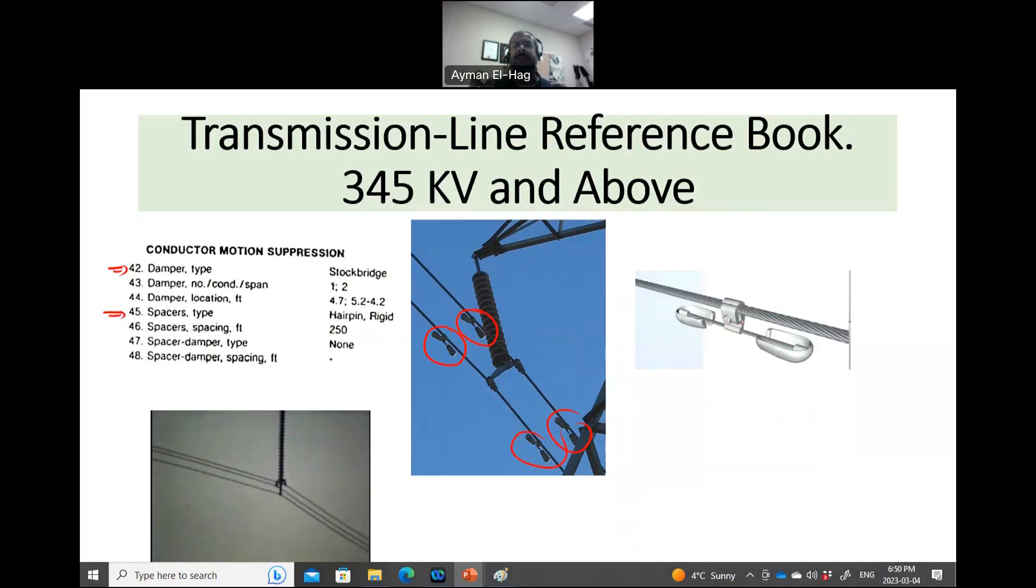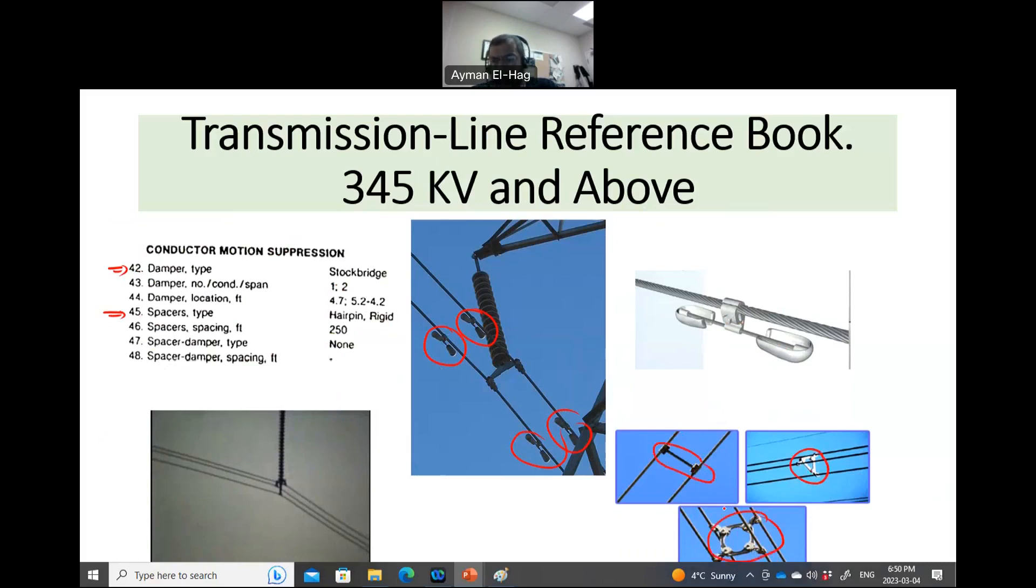Another thing is the spacer. Now, whenever you have more than one conductor per phase, you have to connect these conductors together so that whenever there's wind, they will not be touching or hitting each other. So you keep the space uniform. And this is something important in calculating the inductance and the capacitance. So here, this is a bundle of two, bundle of three, bundle of four. And you have here, you see here the spacer that is connecting these conductors to maintain that space uniform throughout the conductor. So that's, I would say, just an ABC about overhead transmission lines.